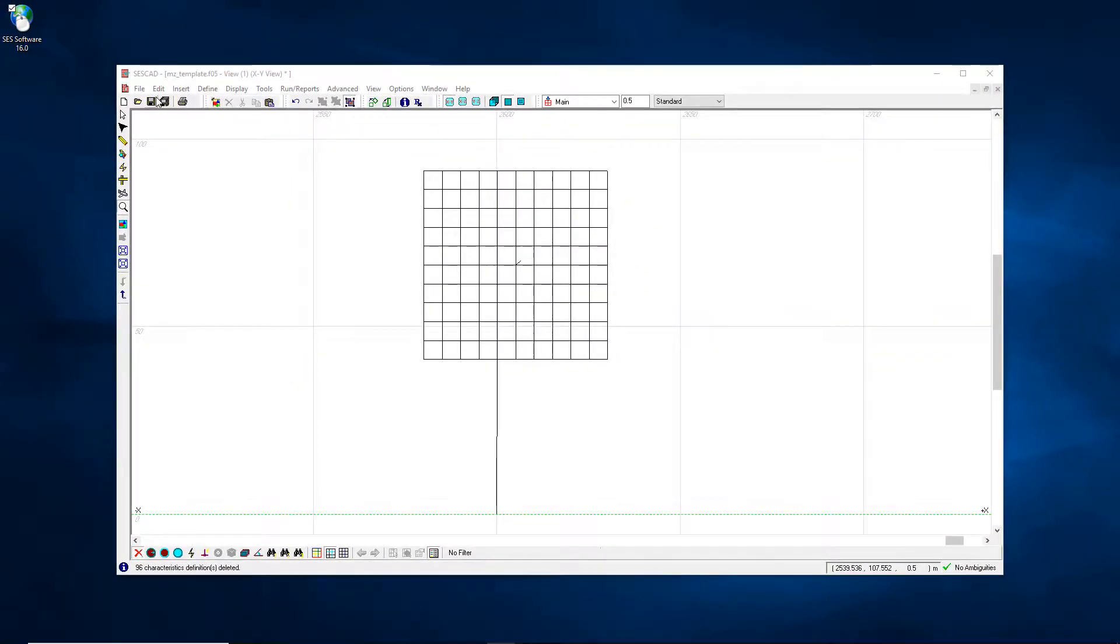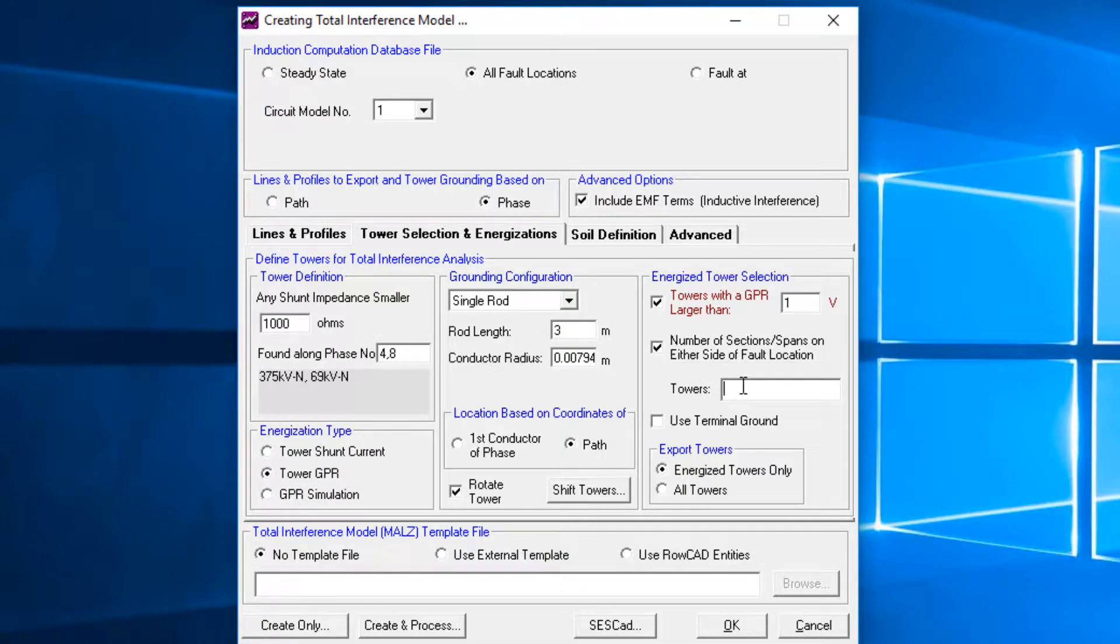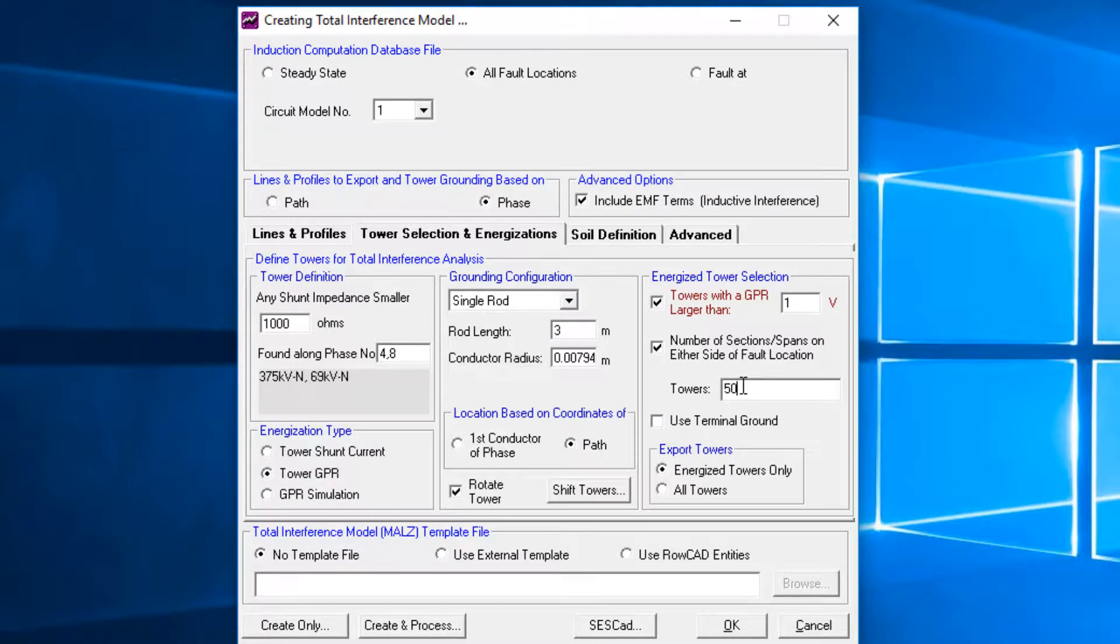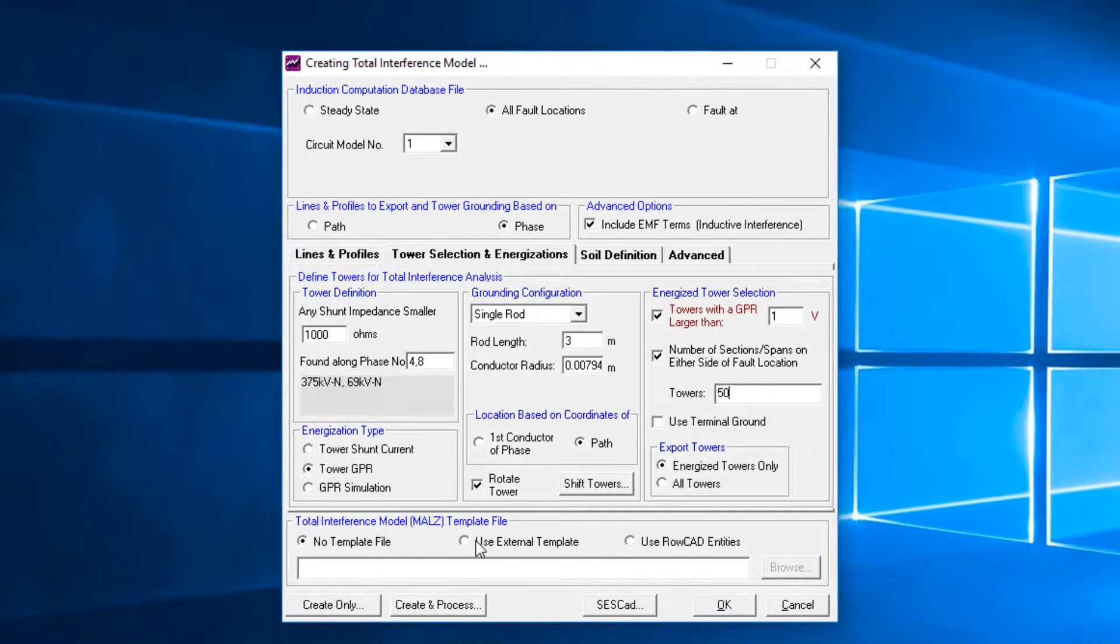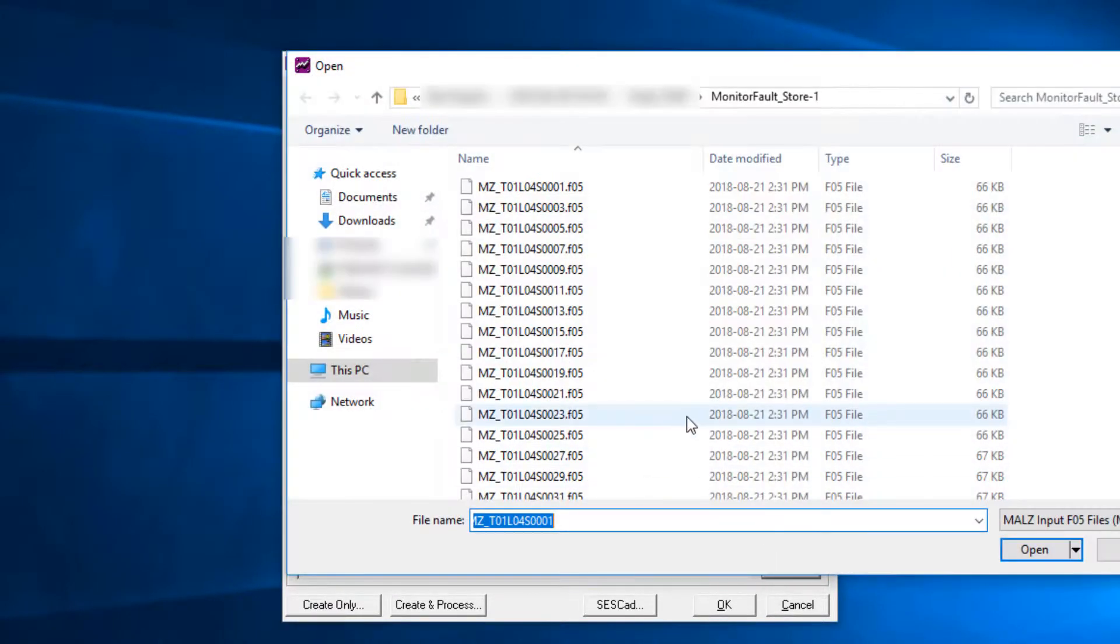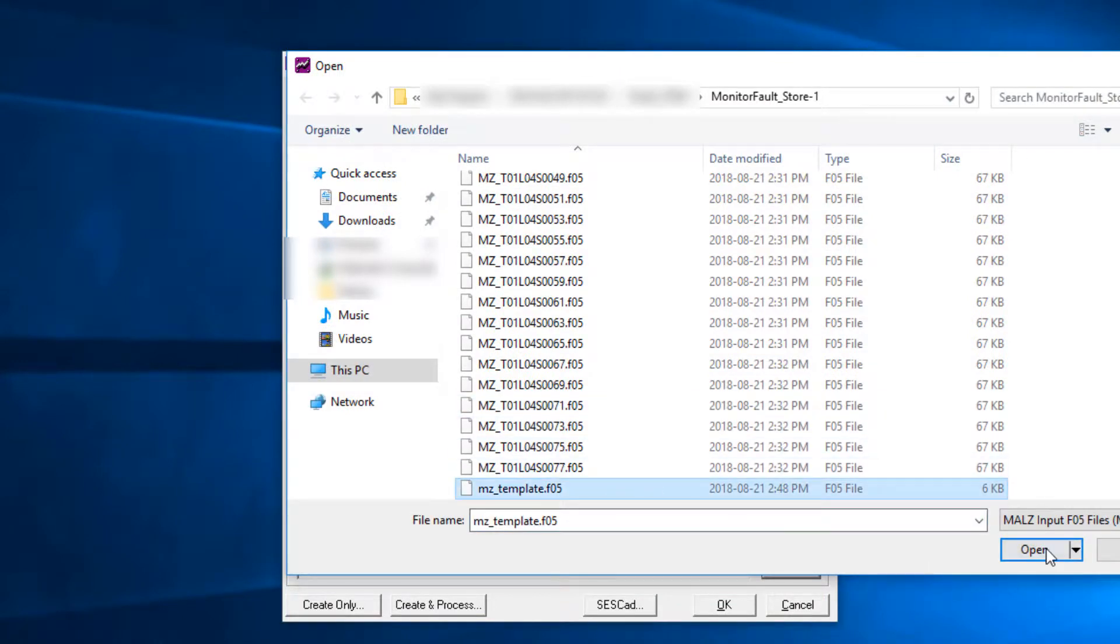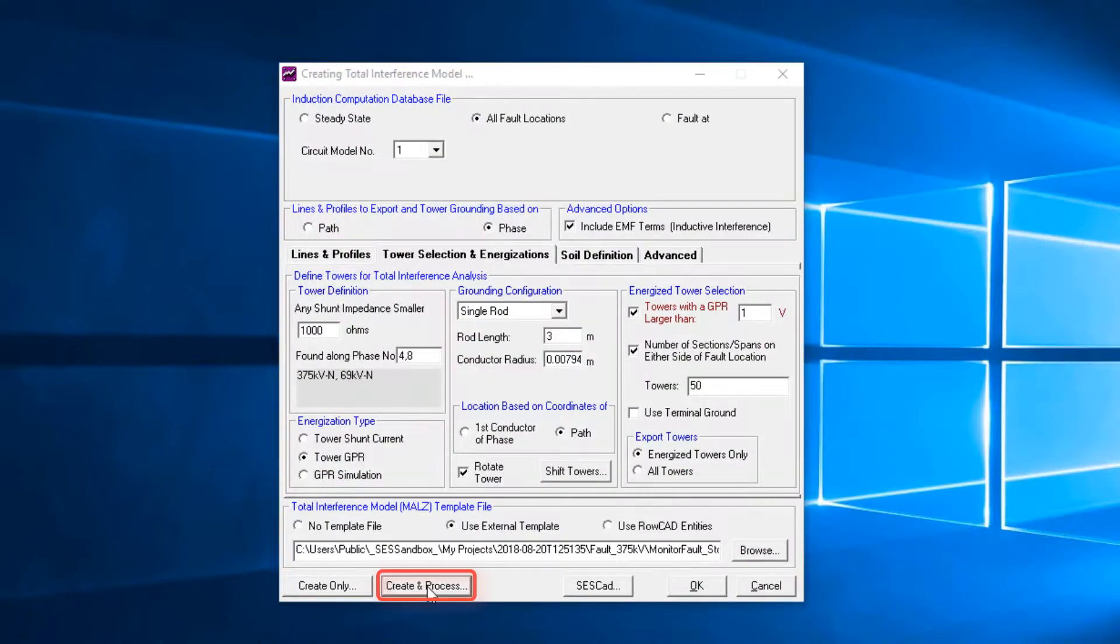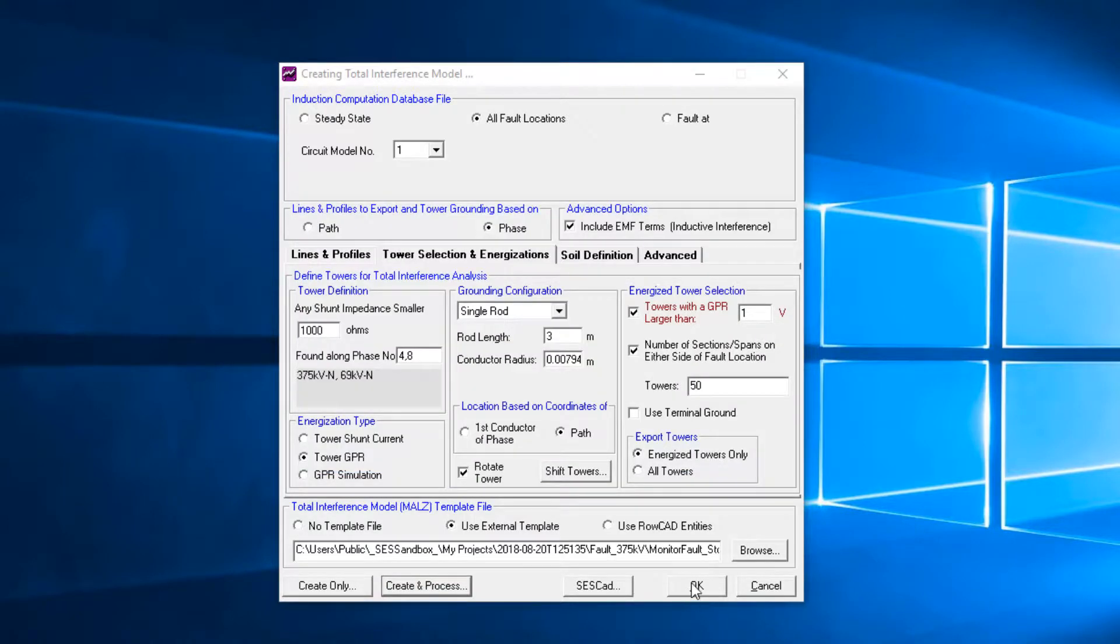Back in the Total Interference module, you can also set the number of towers to be exported to 50 on either side of the fault location to save computation time. Add the reference to MALZ template file. Click the Create and Process button. The files get created and are run immediately in sequence.